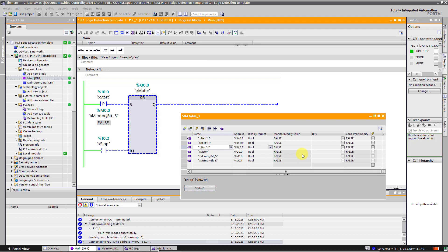Now I will simulate the start button error. OK, so I will turn on this bit. In this scenario, the start button contacts will get stuck closed. In other technical words, this is contact welding.